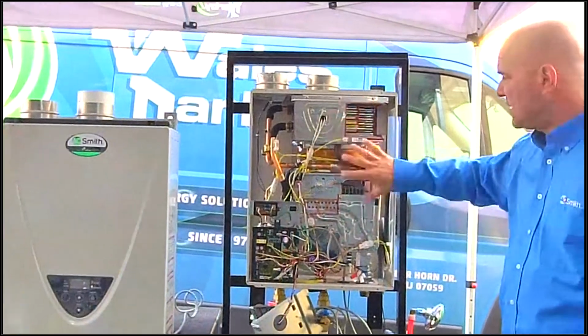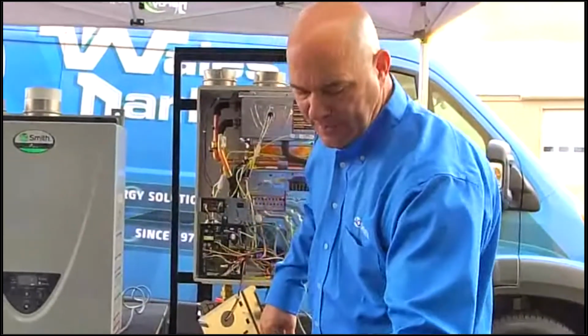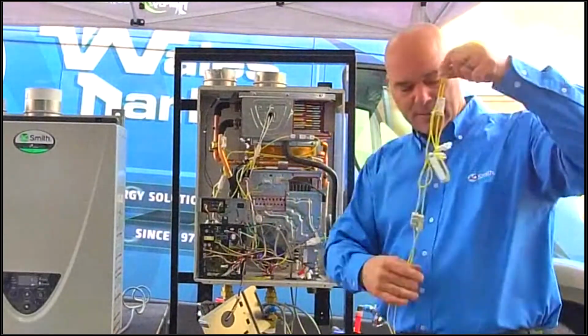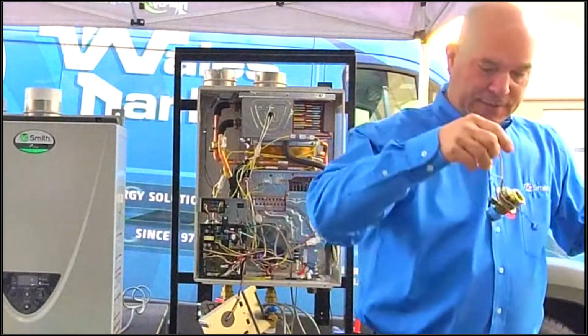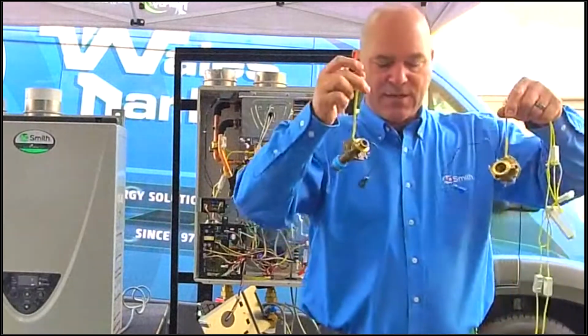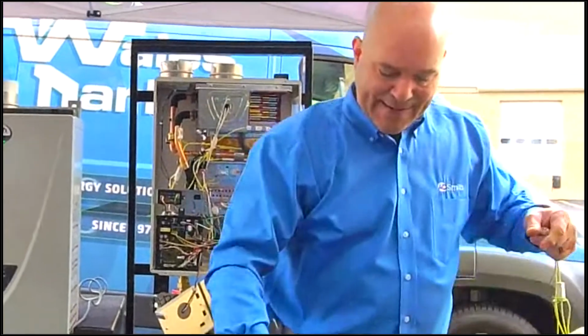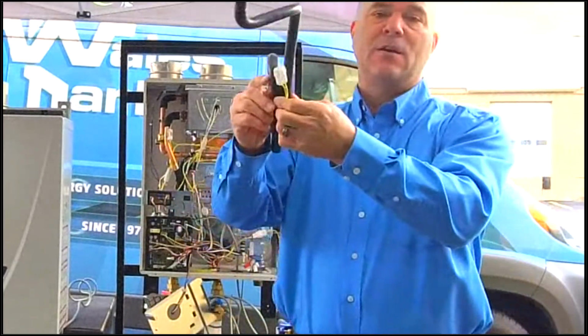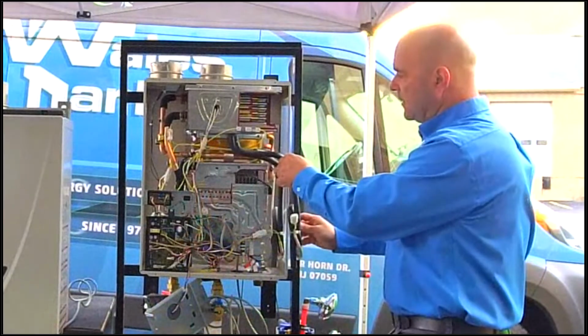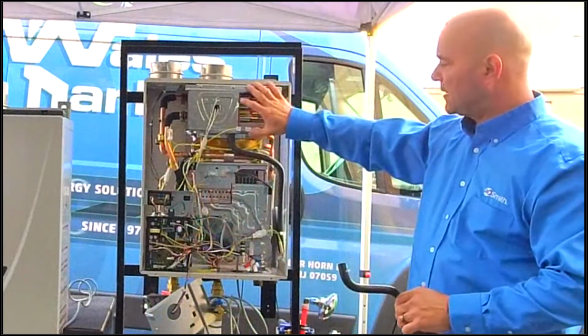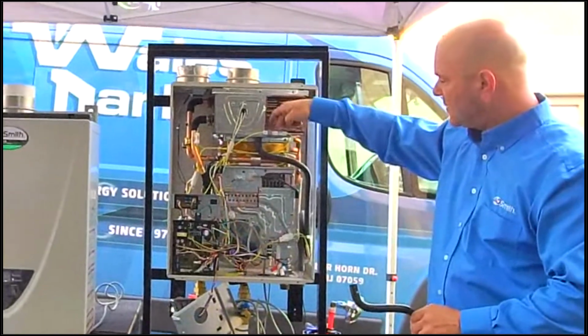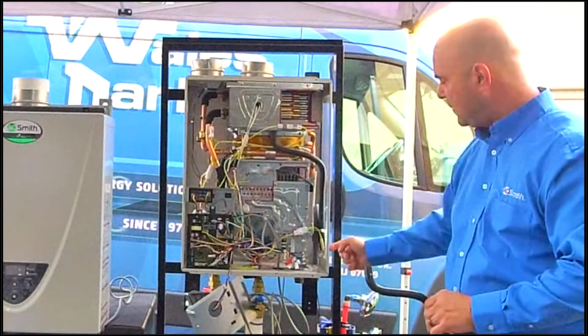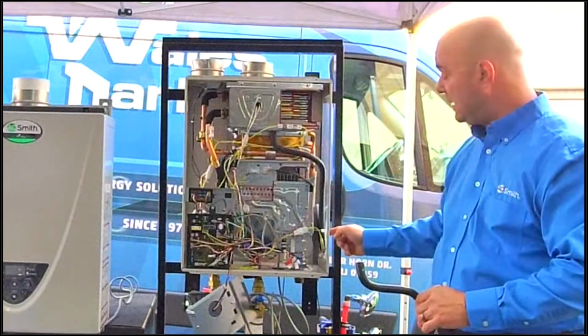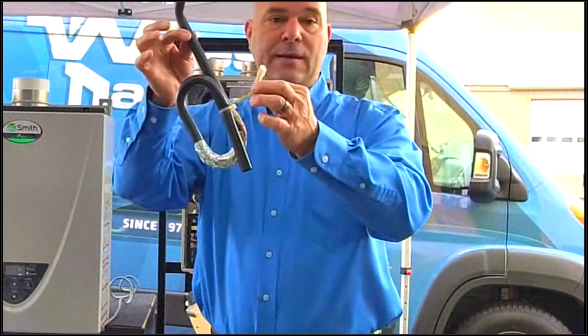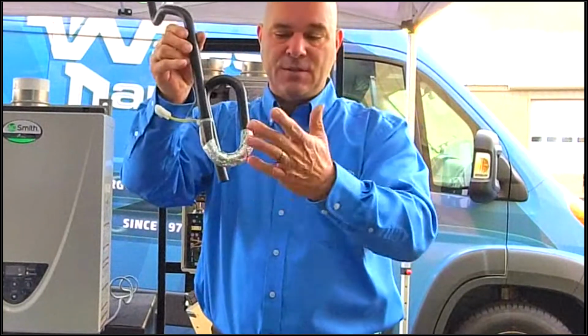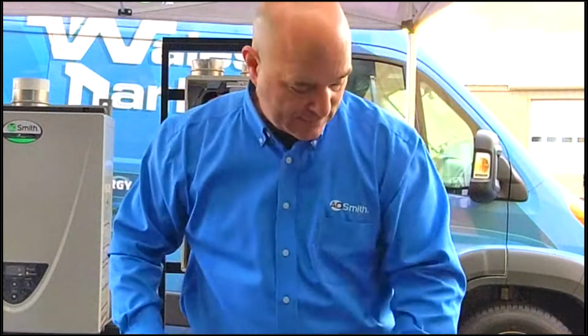In addition to the safety side, we have built in, these are the block heaters I mentioned earlier, and you also see them on the inlet valve and outlet valve, these yellow wires. We condense. This is our condensate trap. That also has a yellow wire. All of the condensing should happen in the secondary heat exchanger. It will condense, run down into this trough, come out, go down through a trap, and it will sit right here. The trap will have water in there. So, yellow wire on the trap. This is a heated trap to make sure that we don't freeze.